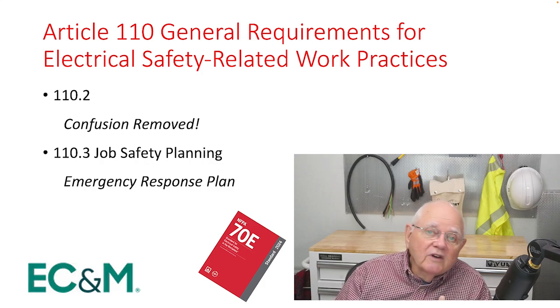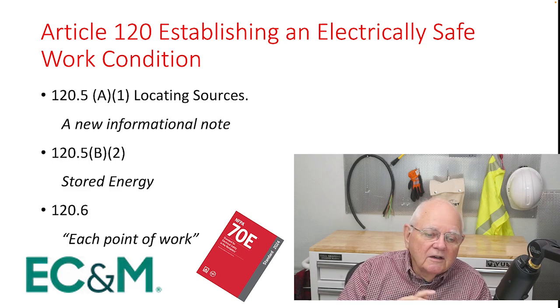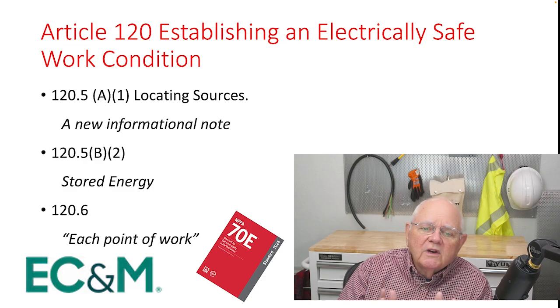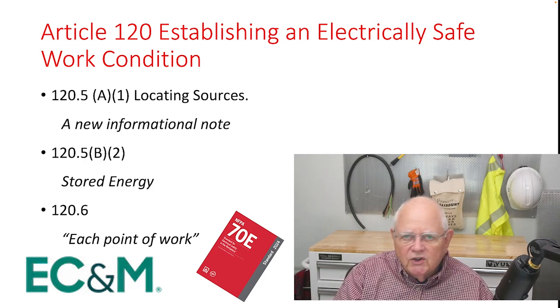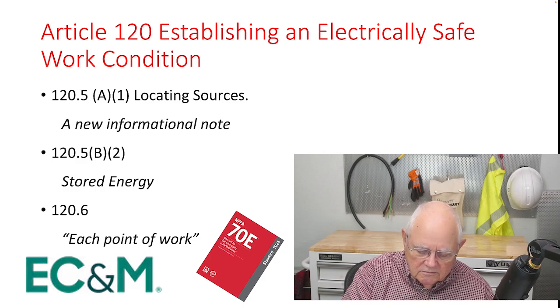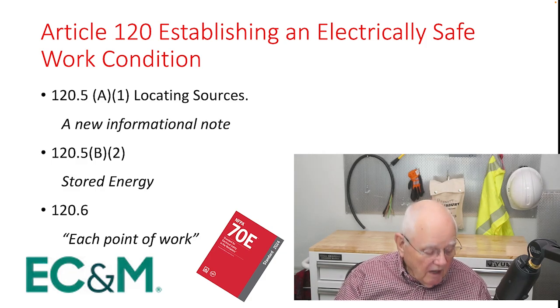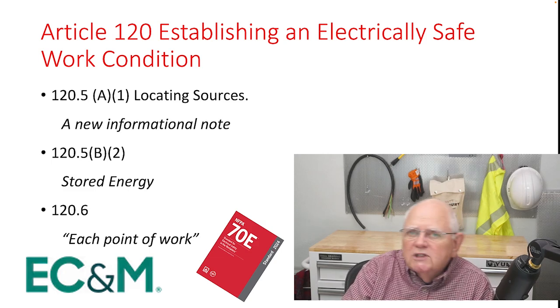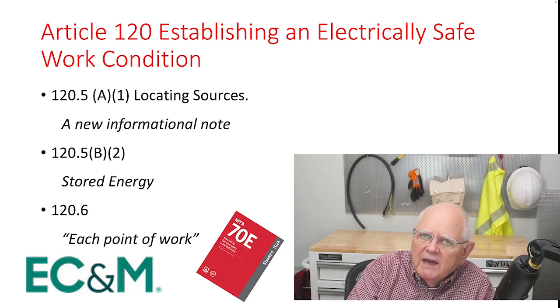Article 120, we've already talked a little bit about that point of work in 120.6 is the term that they use there at the bottom of the screen behind me. But anyway, 120.5, locating sources, has a new informational note. Let's take a look at that informational note. It says, locating sources of supply could include identifying situations where a neutral conductor continues to carry current after phase conductors have been de-energized. So what they're talking about is locating all the different sources of supply, such as maybe a standby generator or UPS battery, something like that.